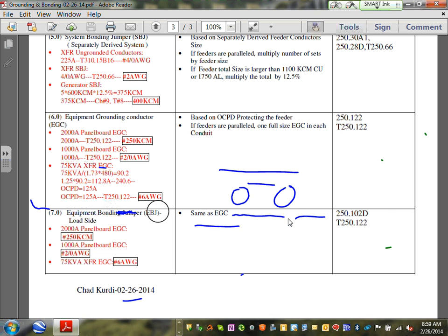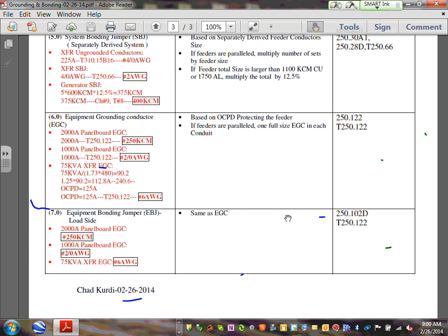So let's go to 7.0, guys, and 6.0. Here we go, right here. So this is what I'm going to try to size right in here. Can you guys see that? This is at the transformer. Now we're coming to the primary. This is called the equipment grounding conductor. The cable that you guys are bringing from here, you see that one? Here's the transformer. The cable that you bring from here to the transformer has to have an equipment grounding conductor with it. On the primary side, that's what I'm sizing.